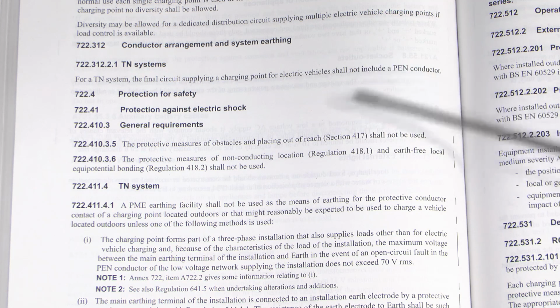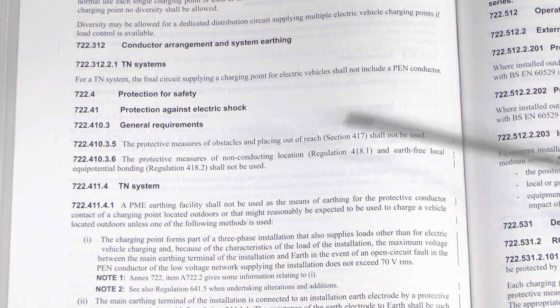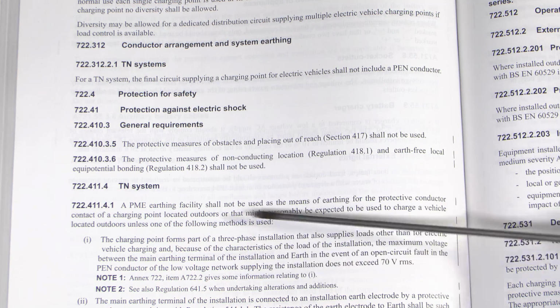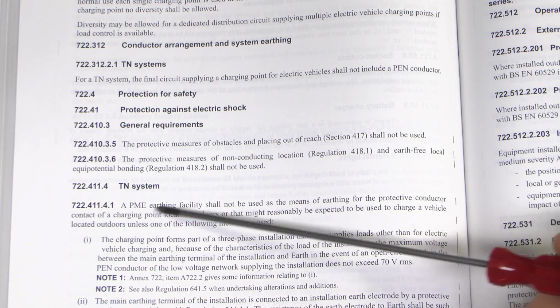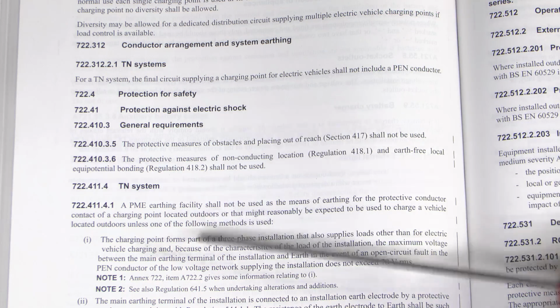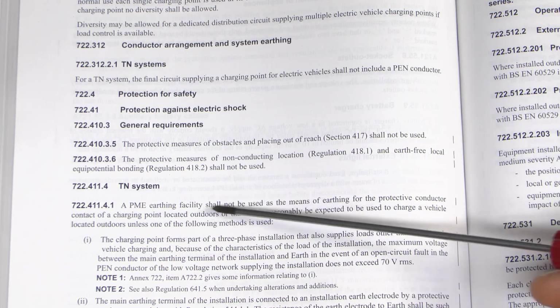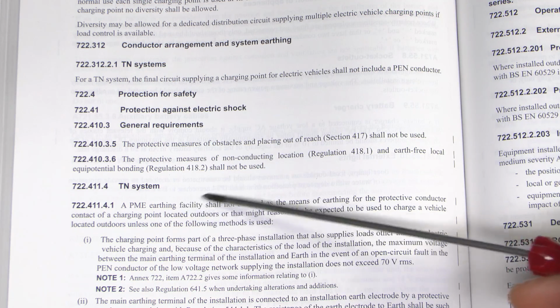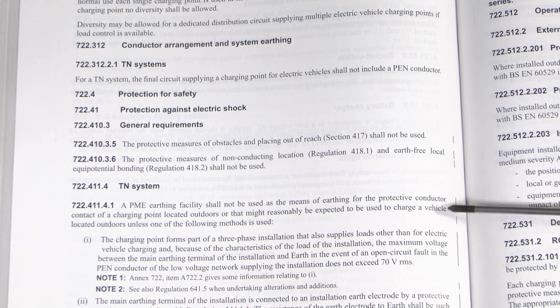And there are some very specific requirements here, particularly in regards to a TNCS or a PME, as it's described here, type of system, in that if you've got one of those, you can't actually use the PME earthing facility as the means of earthing for the protective conductor of the charging point. Now, a lot of properties have PME or TNCS supplies, and of course this is certainly going to be a problem if you're not actually allowed to use it.